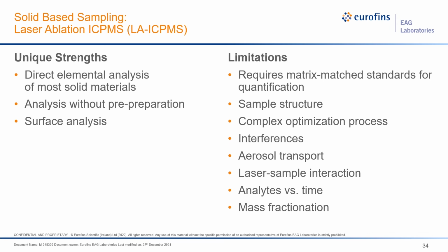So the unique strengths of laser ablation ICP-MS is that it provides surface and near surface analysis, analysis without pre-preparation at all, and the direct elemental analysis of most solid materials. Its limitations are that it does require matrix-matched standards for quantification. We're limited by sample structure and sample homogeneity.